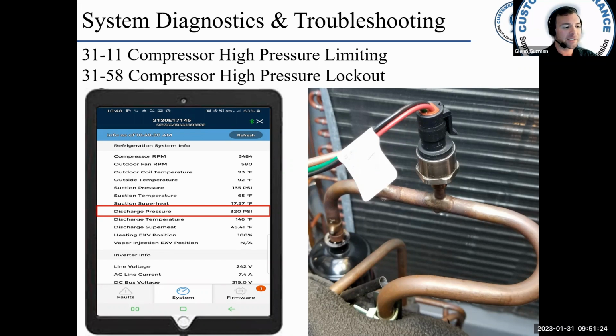Okay, so the goal behind this is to keep the compressor operating in the envelope within limits. It's trying to maintain operation the best it can, but it's not going to allow the compressor to drive itself into the ground. Each hour of compressor operation without a fault will increase the compressor speed limit by 25% until it can get back to 100% of operation. 3158 occurs when the high pressure limit is reached while the compressor is at its minimum operating speed, and then you get a lockout for 2 hours.